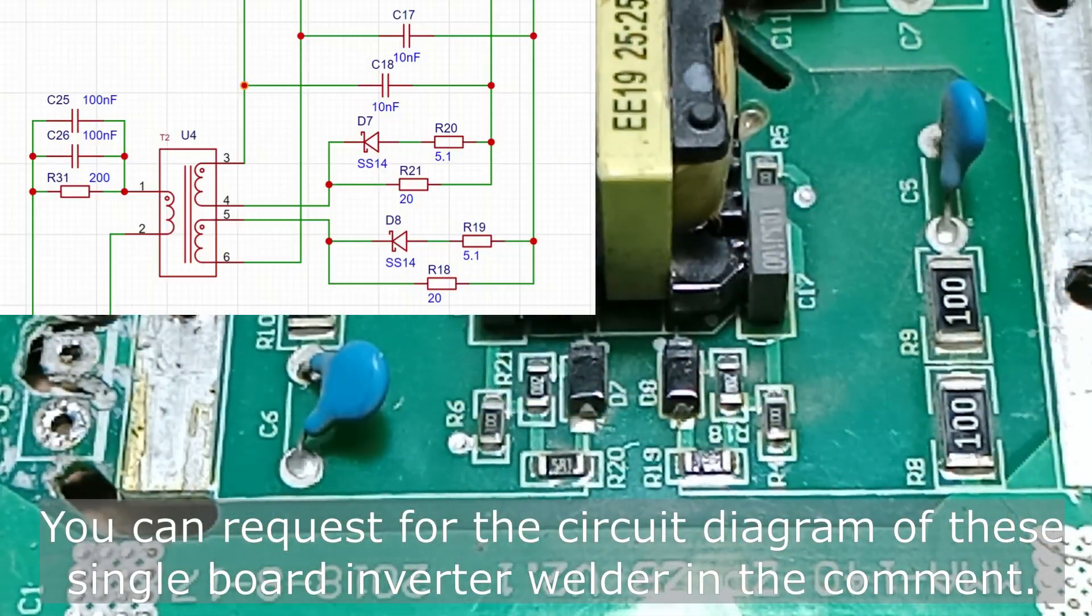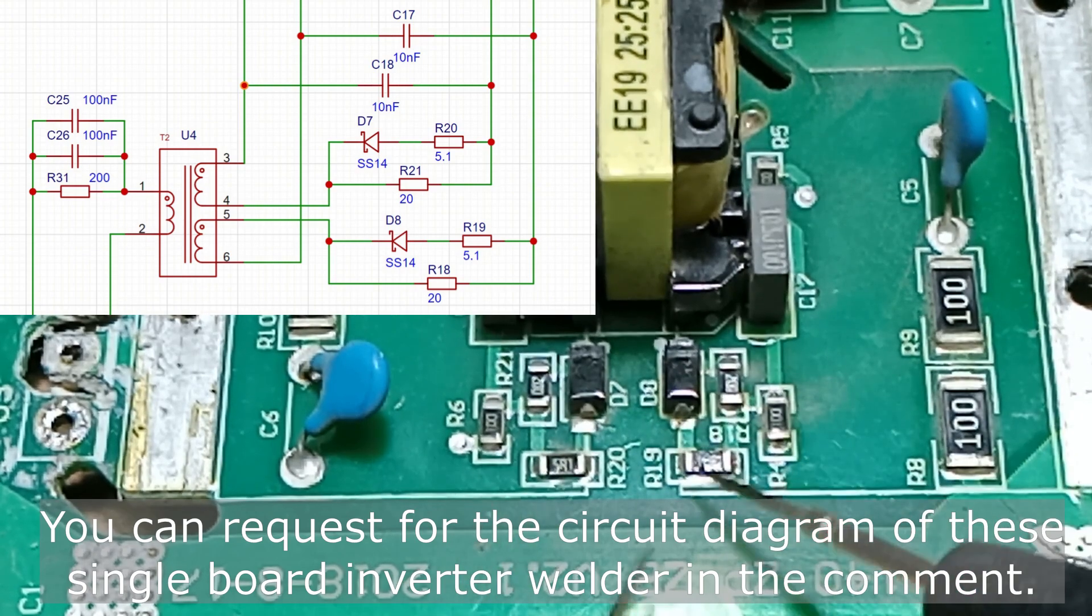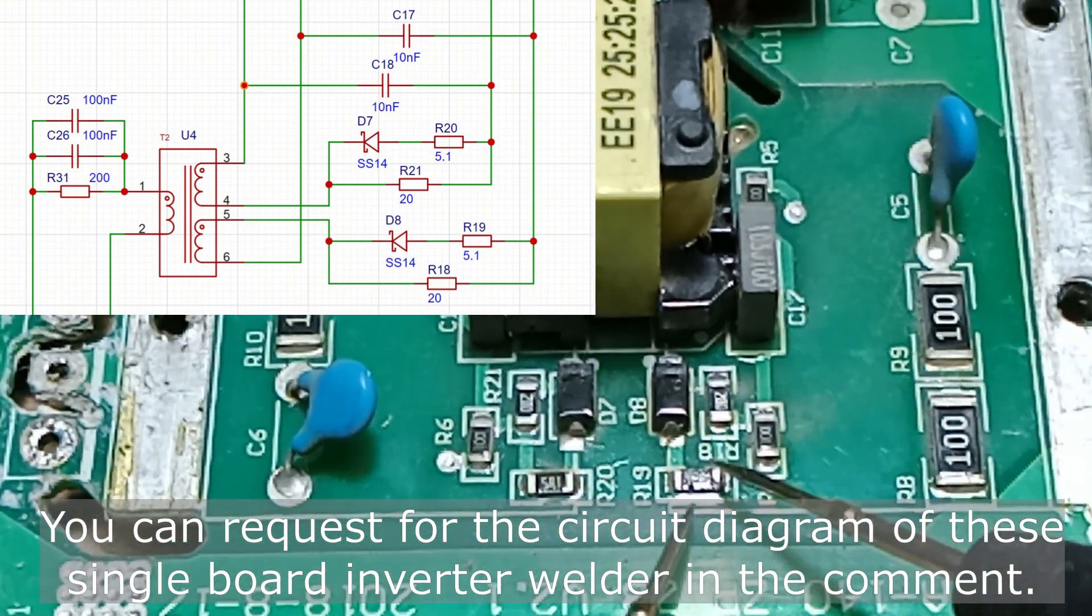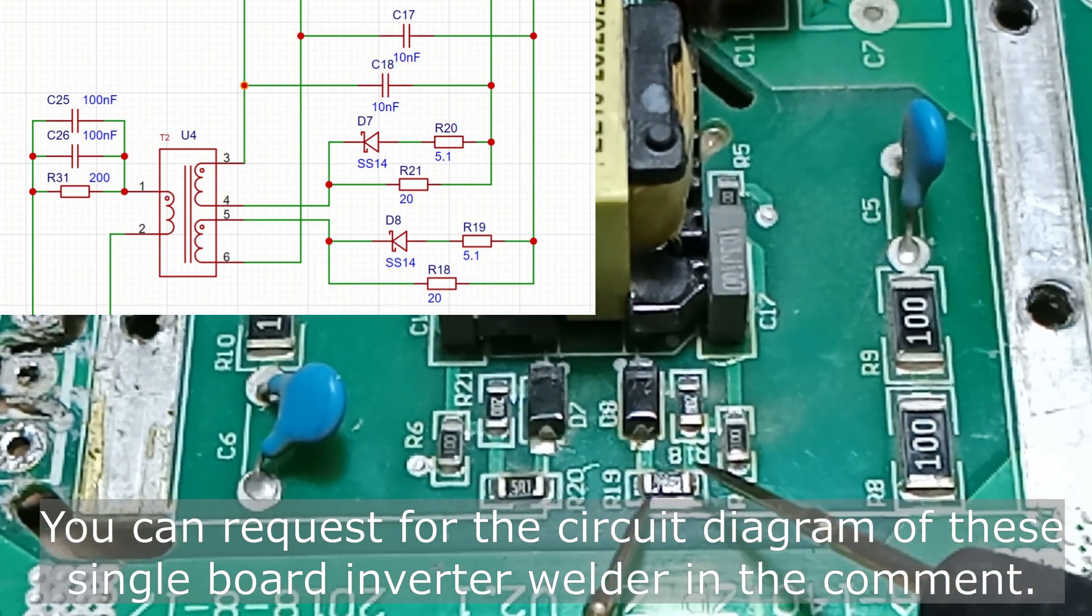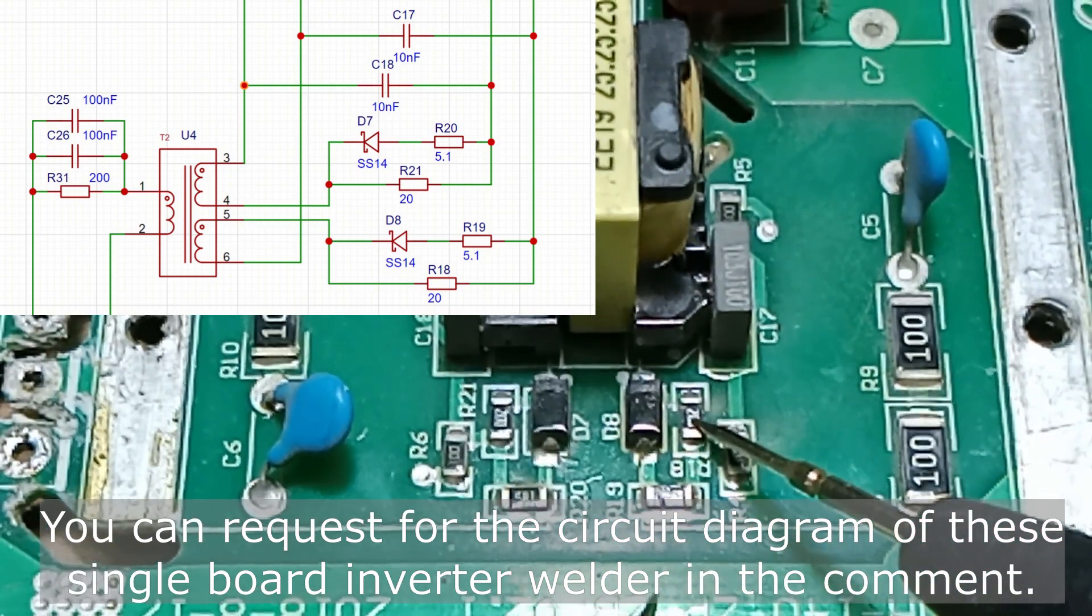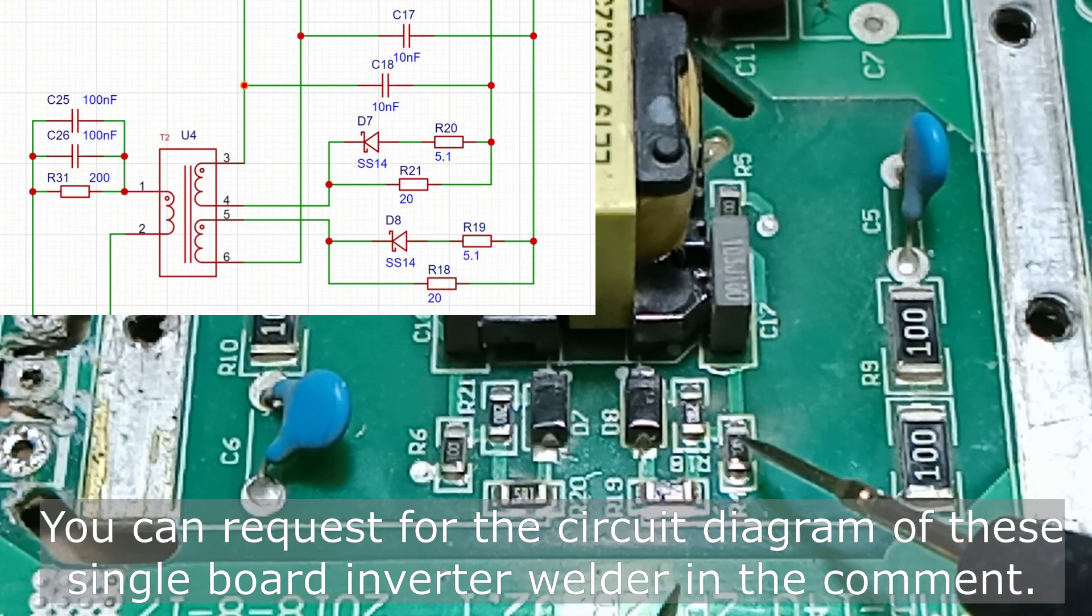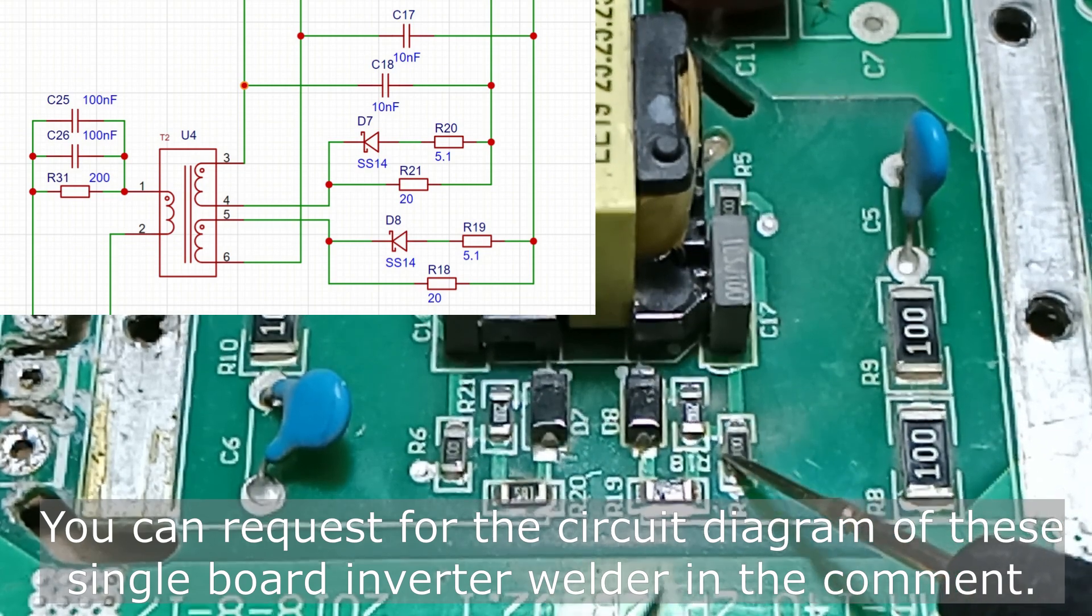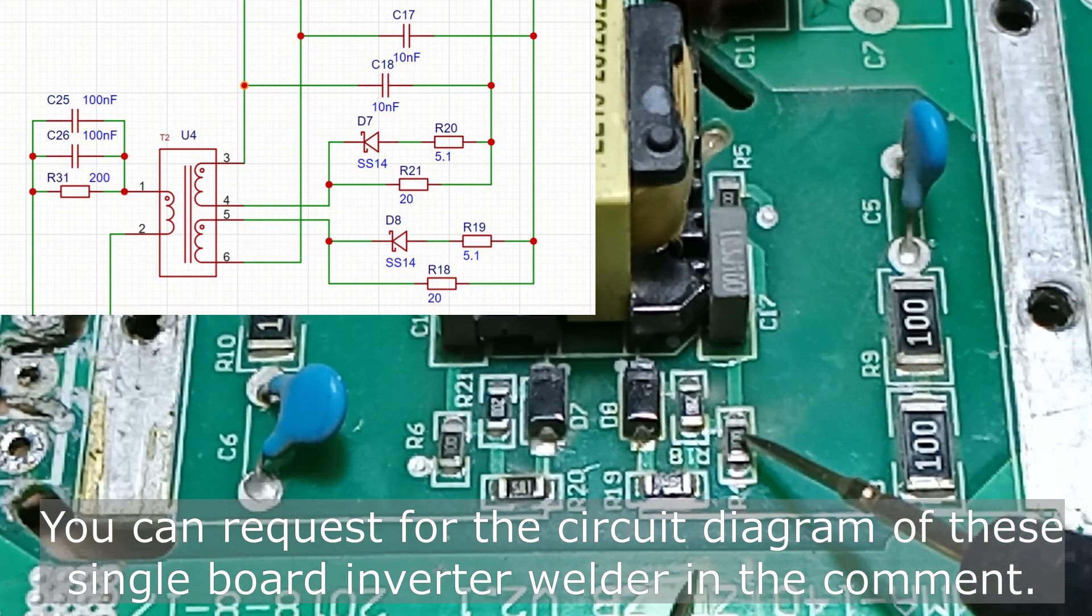Whenever the IGBT is broken, you always want to check the components of the gate drive circuit. There are resistors, diodes, and a few capacitors that sometimes get burned out together with the IGBT. Fortunately for this board, they all look fine.